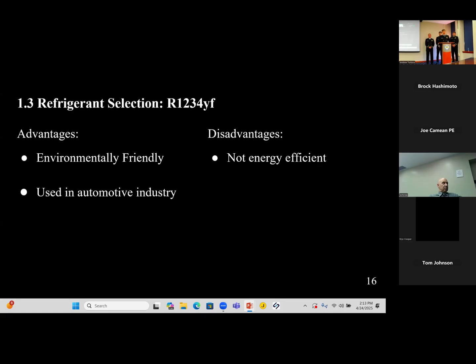Now, before we get to our final decision, the last one we're going to talk about is R1234YF, which is a common refrigerant in the automotive industry. It has a low global warming potential as a refrigerant, but the disadvantage is it's not as energy efficient, and it's about 8 to 10% less cooling capacity per the amount that the compressor is working. So for that reason, you're going to be burning more. You're going to have more emissions coming from your generators if you're running MDO, and even so, you're going to be running your generators more, burning through more fuel. And for that reason, we decided not to go with this refrigerant.